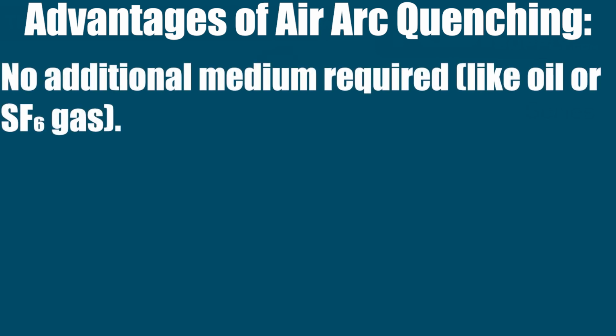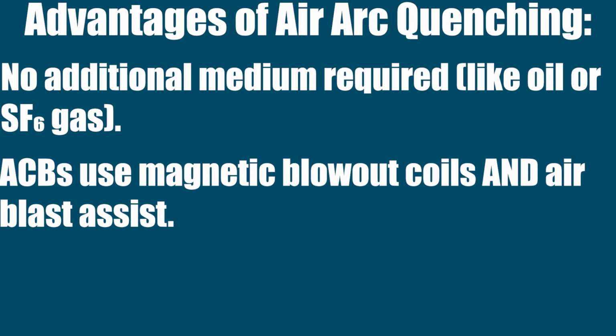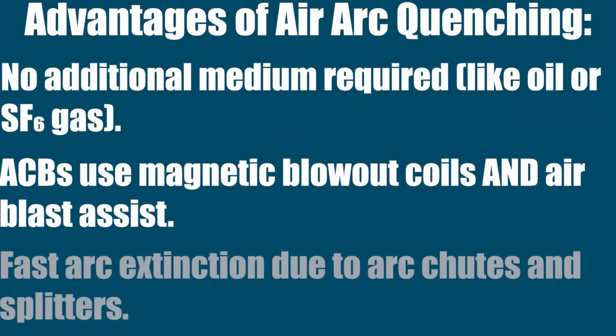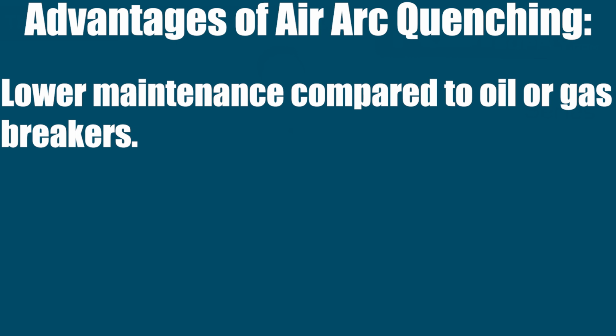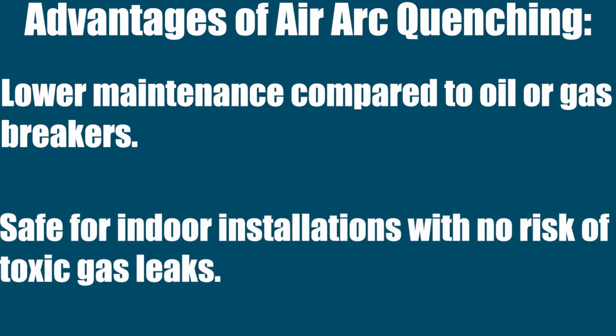Some advantages of air arc quenching are that there's no additional medium required, like oil or gas. Air circuit breakers also use magnetic blowout coils and air blast assist. Fast arc extinction due to arc chutes and splitters, longer ones. They also have lower maintenance compared to oil or gas breakers. They're safer for indoor installations with no risk of toxic gas leaks.